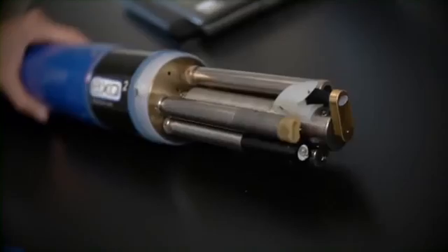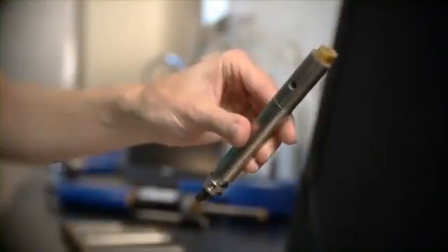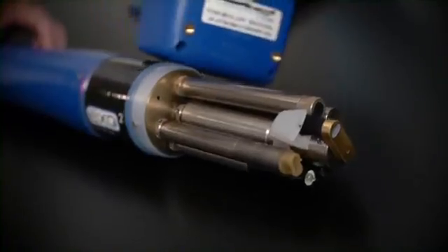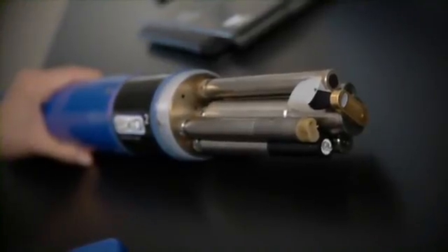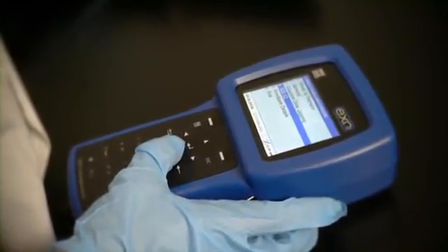The Exo-2 has a unique ergonomically shaped outer body with an internally reinforced composite framework. Wet-matable connectors. A unique hermaphroditic design prevents misalignment during installation of the sensors and is insensitive to moisture. Plus, handy Bluetooth communication in a range of anti-fouling components such as wipers and sensor coatings. Sondes come standard with visual indicators to quickly determine if the sonde is on, on and in logging mode, has an internal fault or off.